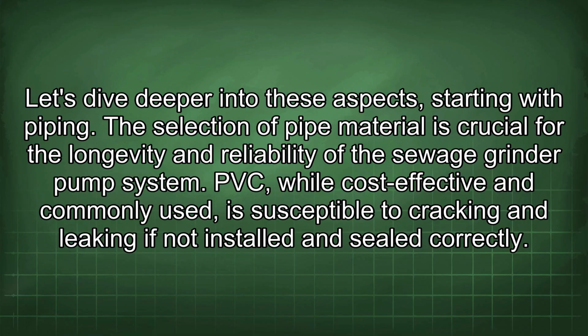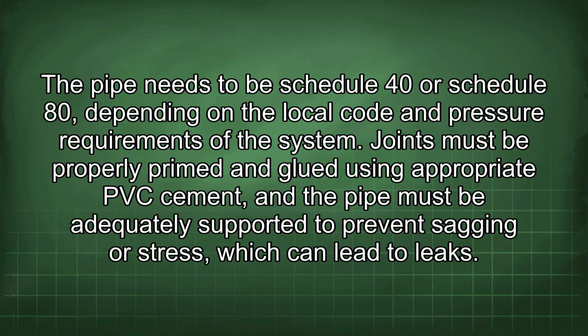PVC, while cost-effective and commonly used, is susceptible to cracking and leaking if not installed and sealed correctly. The pipe needs to be Schedule 40 or Schedule 80 depending on the local code and pressure requirements of the system. Joints must be properly primed and glued using appropriate PVC cement, and the pipe must be adequately supported to prevent sagging or stress, which can lead to leaks.